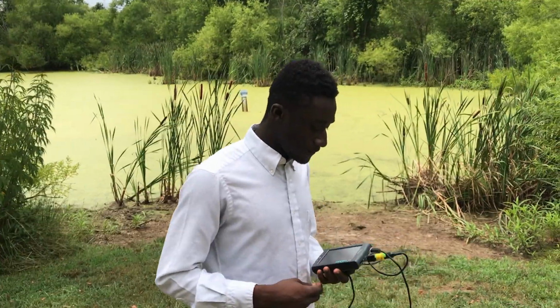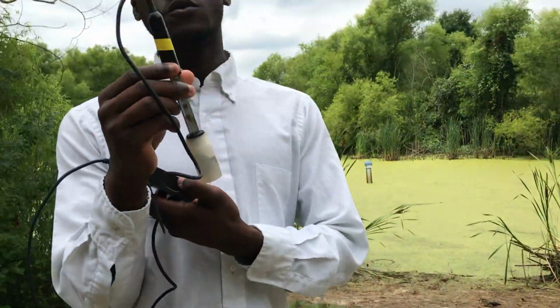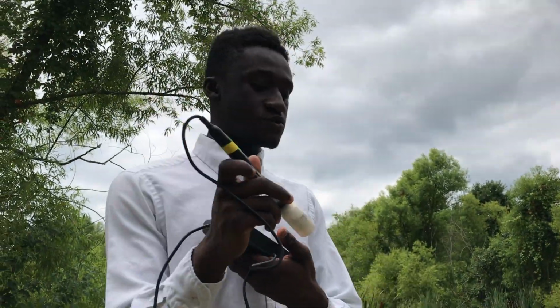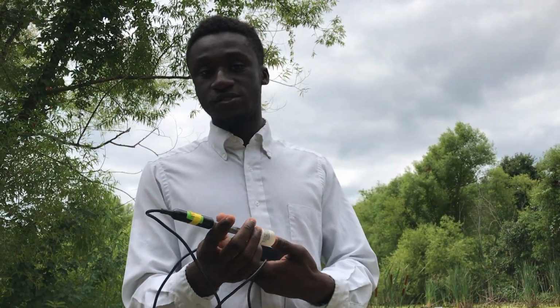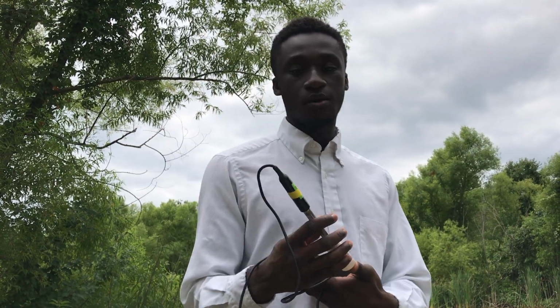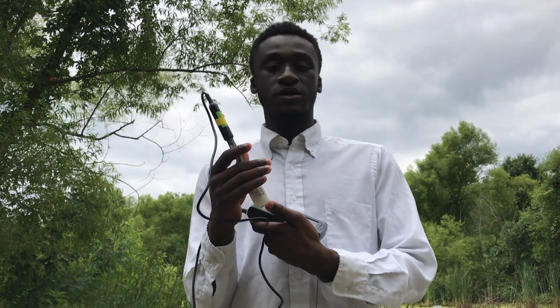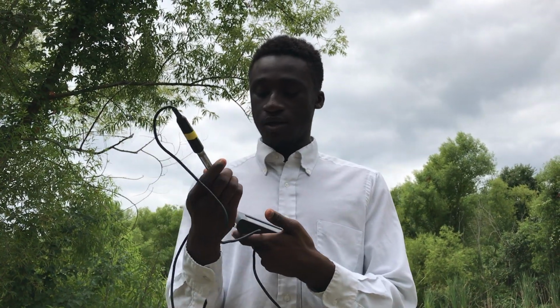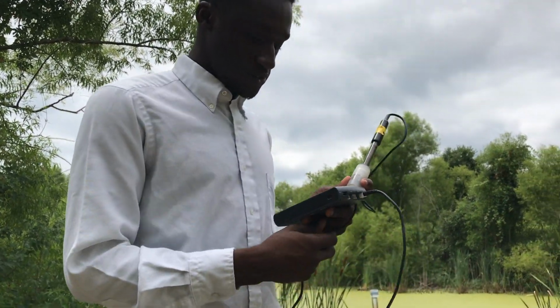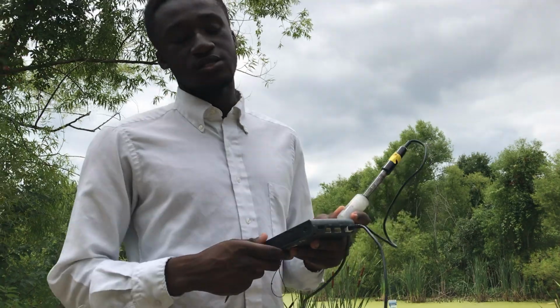So we'll ensure first that the solution that we have, just as with the nitrate probe, the original solution that this came in had a seal. And so if it did not have a seal, maybe you have an issue with your solution and you should immediately stop and figure that out. But with this solution, we know we've been soaking in it, we know where we got this, and we know it was fine. So we're gonna basically just use it to calibrate it because it's the same calibrating solution.